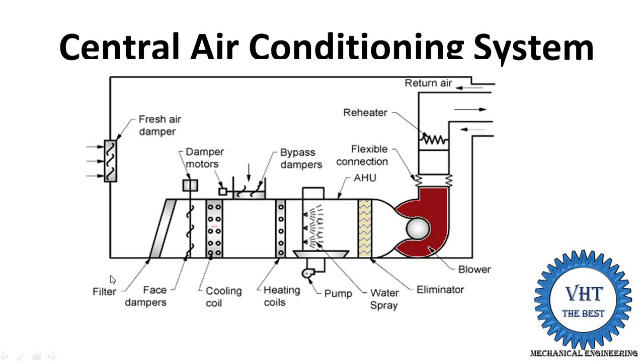Now step by step, let us understand the function of each component. Fresh air comes in through the dampers. This fresh air damper is operated by a thermostat, which measures the return air temperature or room air temperature, and on that basis supplies fresh air to the AHU unit. The air is filtered and then supplied to the dampers. The damper controls the quantity — the mass flow rate — of air supplied to the cooling coils.